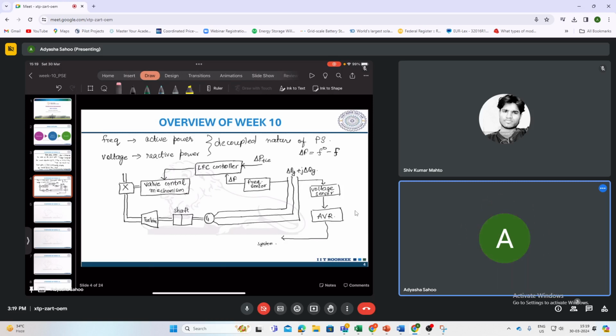And let me draw it near to the field of the generator. So the generator field is here, and here we have the excitation system. Right. So this is how we control the active and reactive power in order to control the frequency and voltage in the system. So in this week we will be mostly concerned with the active power and frequency control. The voltage and excitation part is not covered here.